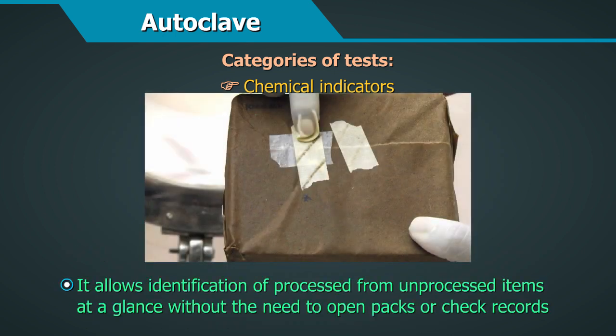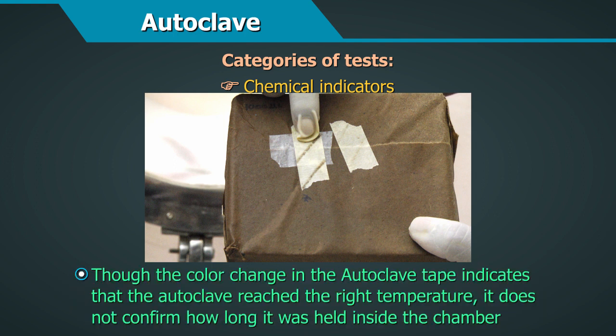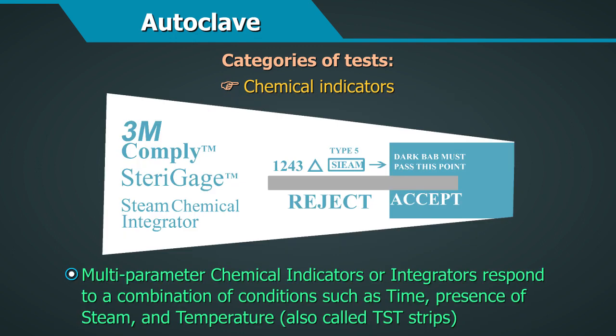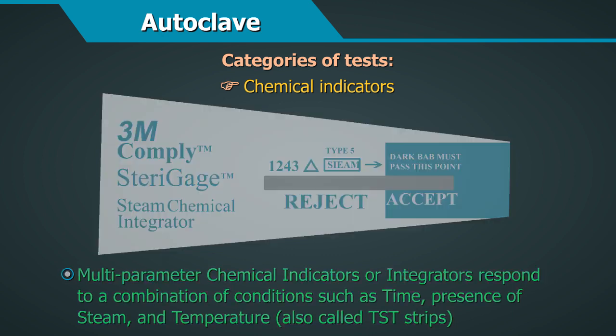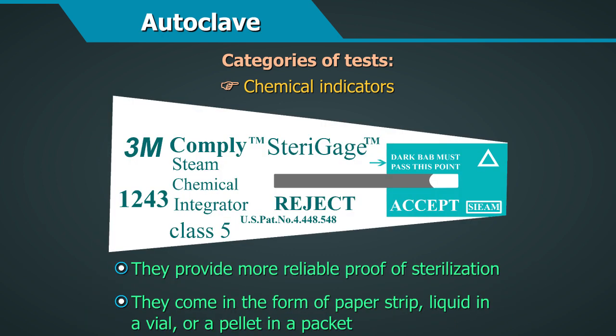It allows identification of processed from unprocessed items at a glance without the need to open the packs or check the records. Though the color change in the autoclave tape indicates that the autoclave reached the right temperature, it does not confirm how long it was held inside the chamber. Multi-parameter chemical indicators or integrators respond to a combination of conditions such as time, presence of steam, and temperature, also called TST strips. These provide more reliable proof of sterilization. They come in the form of a paper strip, liquid in a vial, or a pellet in a packet.